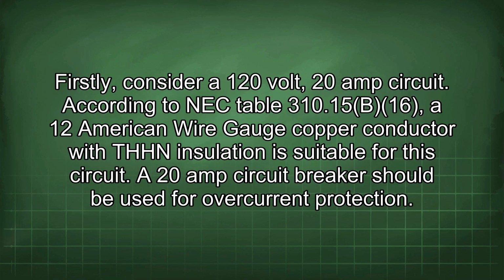Firstly, consider a 120 volt, 20 amp circuit. According to NEC Table 310.15(B)(16), a 12 American wire gauge copper conductor with THHN insulation is suitable for this circuit. A 20 amp circuit breaker should be used for overcurrent protection.